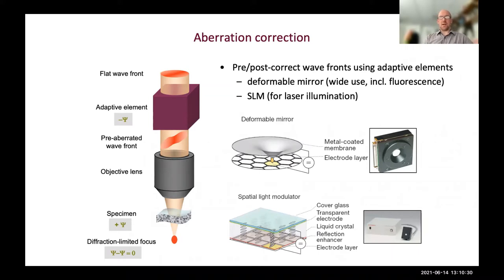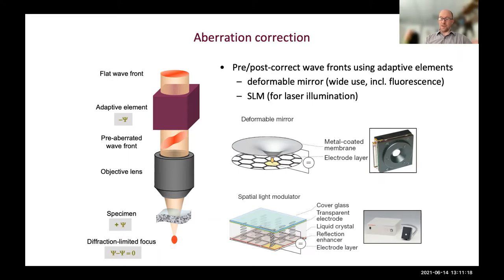We also use liquid crystal spatial light modulators, which work by using electrodes to change the state of liquid crystal materials, effectively exhibiting a different refractive index at each pixel. This allows us to control the spatial pattern of the phase of reflected light. These tend to be best used in laser illumination paths because they require polarized light for operation and have more chromatic effects. For a two-photon microscope, where we only need to think about the quality of light on the way in, a spatial light modulator is very commonly used.